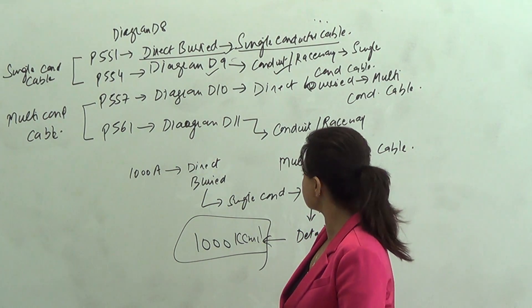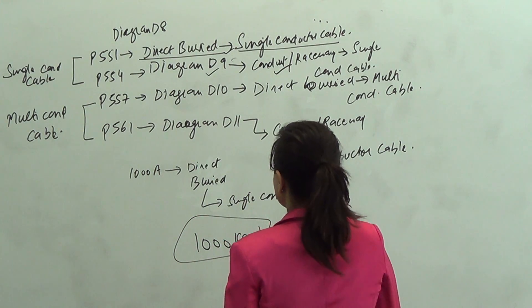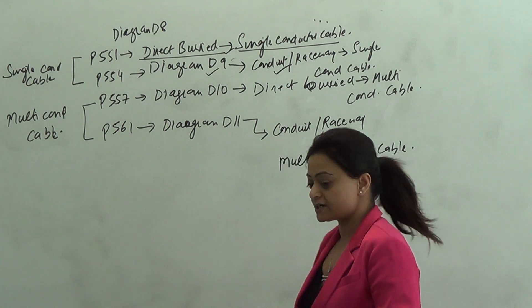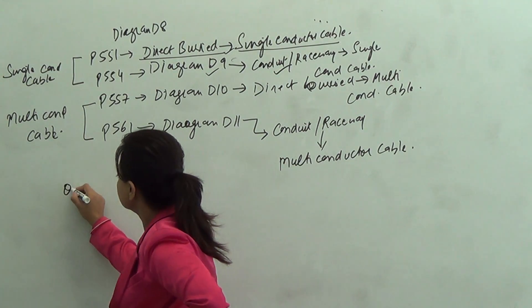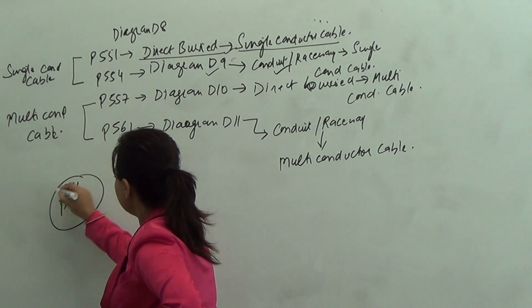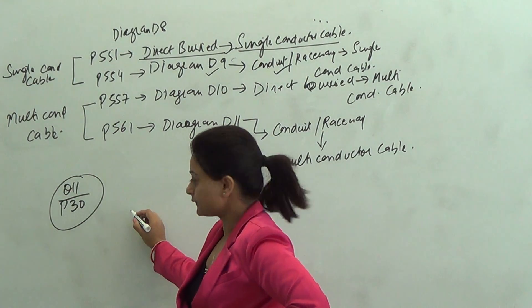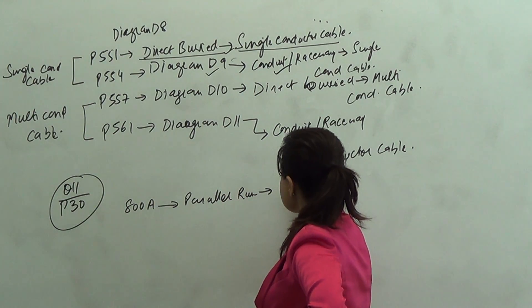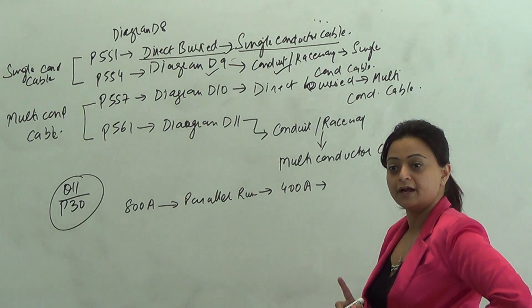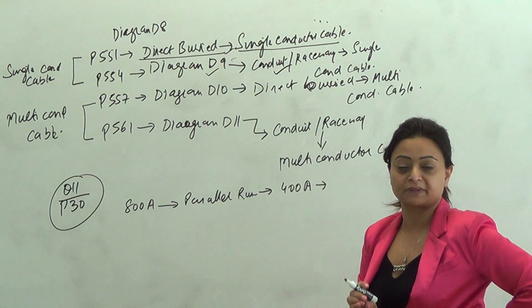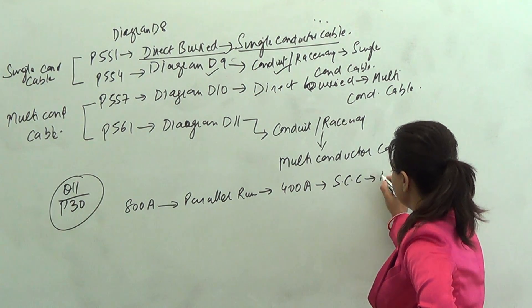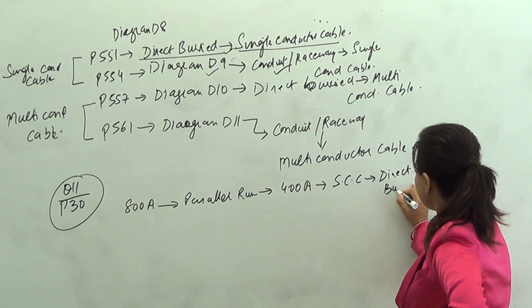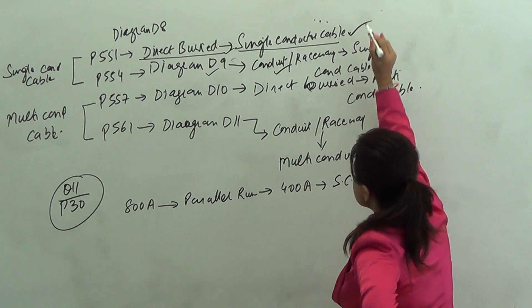Now let's go ahead and do the questions together. Question number 11, page 30 of our binder. I am given total ampacity of 800, and I am doing a parallel run, so the ampacity of each cable is 400. Is it copper or aluminum? Directly buried and single conductor cable — yes, it says it's directly buried. So single conductor, direct buried — first diagram, which is diagram D8.